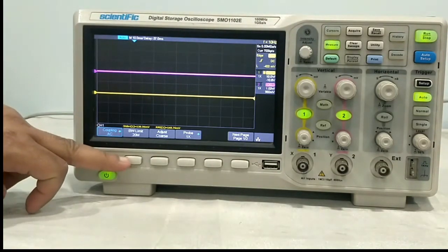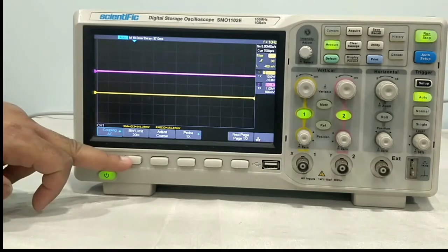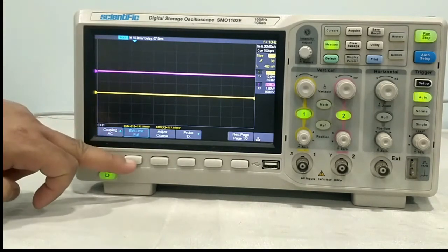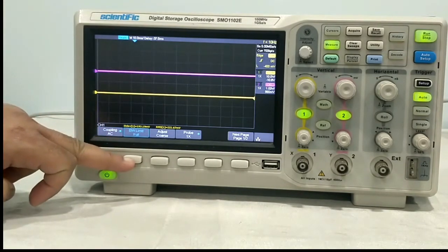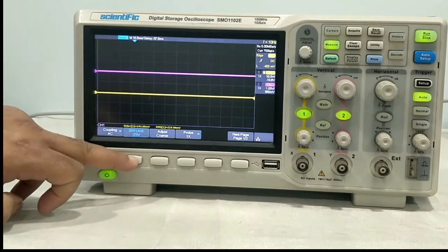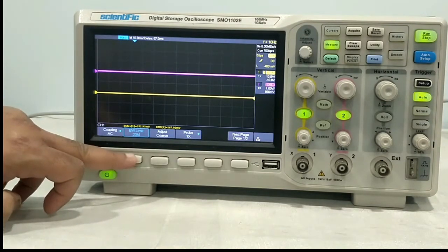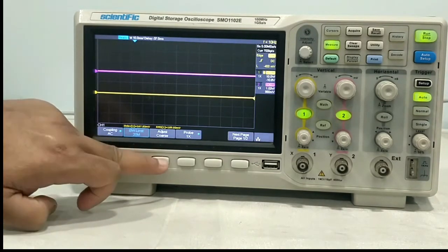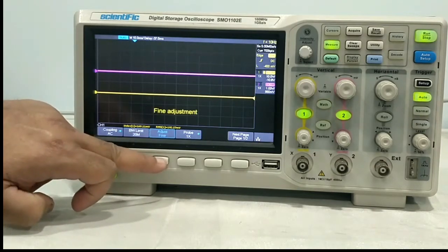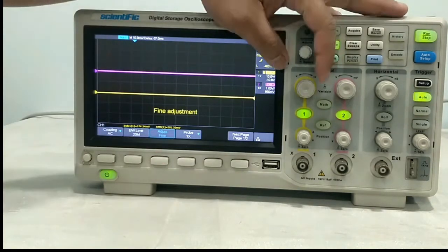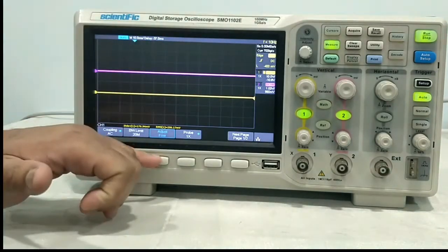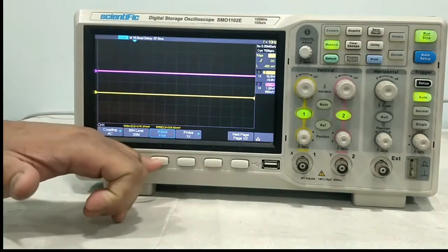Next comes bandwidth limit. From here you can limit the bandwidth to full or to 20 MHz. Next, the adjust is coarse or fine — this is for volt per division. If you want the volt per division to be adjusted in fine mode, you can set it from fine or coarse from here.